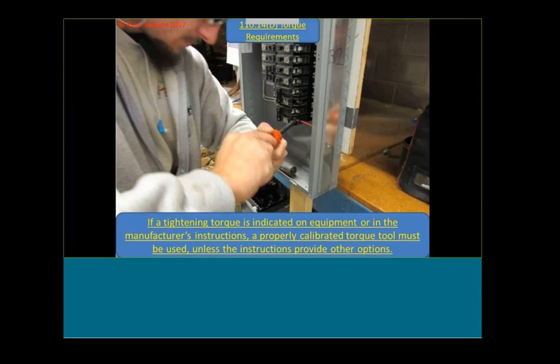They made a change in 110.14D, and this is a big issue in the industry. Everybody's talking about this. It says if a tightening torque is indicated on equipment or in the manufacturer's instructions, a properly calibrated torque tool must be used unless the instructions provide other options.